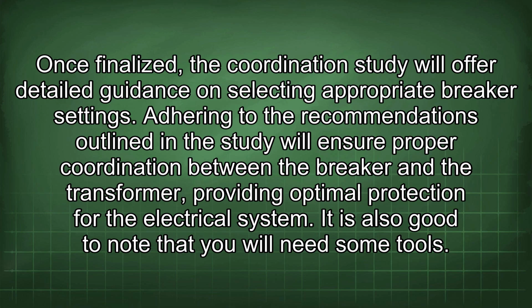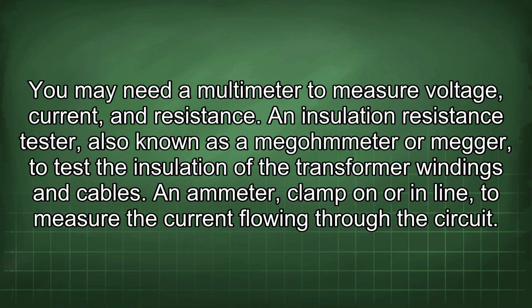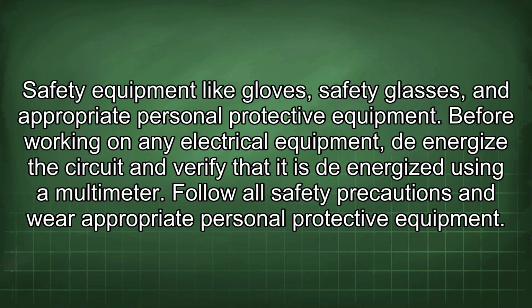It is also good to note that you will need some tools. You may need a multimeter to measure voltage, current, and resistance. An insulation resistance tester, also known as a megohmmeter or megger, to test the insulation of the transformer windings and cables. An ammeter, clamp-on or in-line, to measure the current flowing through the circuit. Safety equipment like gloves, safety glasses, and appropriate personal protective equipment.